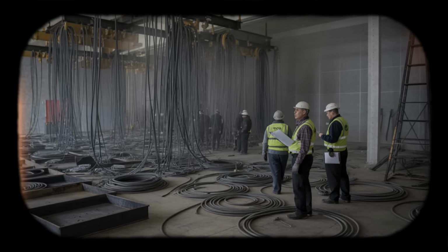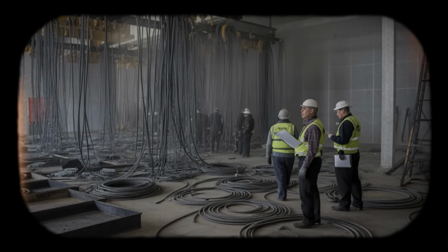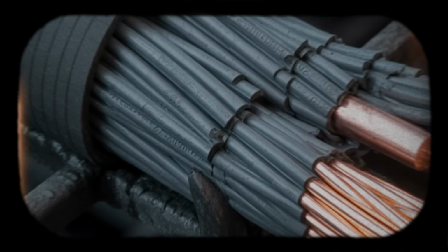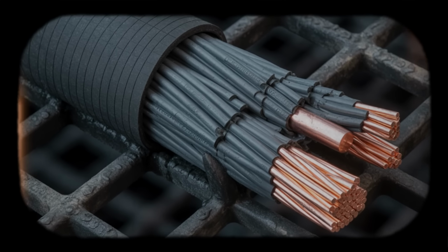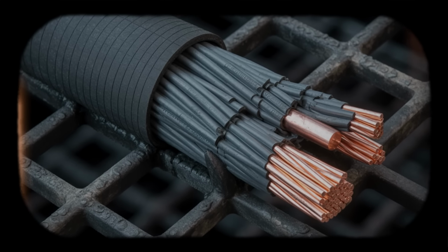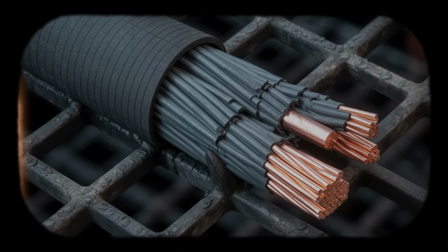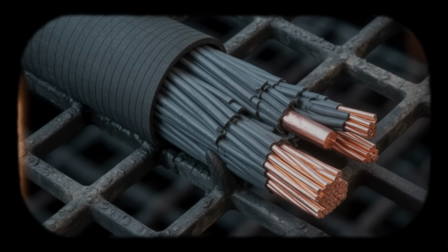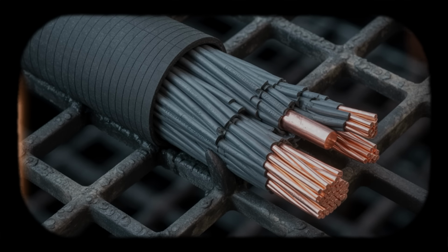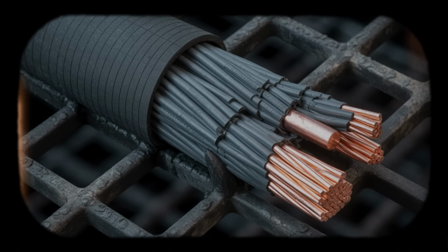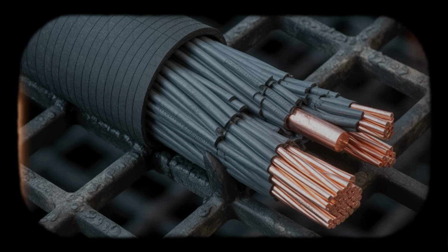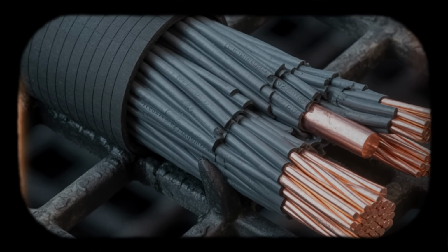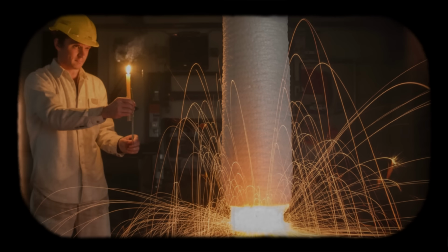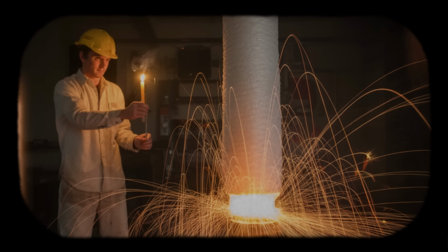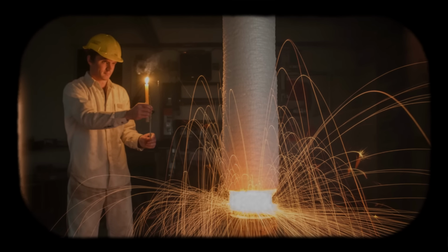but the design included one shared space, the cable spreading room beneath both control rooms. It was an efficiency measure during construction. Rather than building two completely separate cable routing facilities, engineers created one room that served both units. Cables from Unit 1 and cables from Unit 2 converged in the same trays, passed through adjacent penetrations, and shared common support structures. The fire ignited in a penetration that served primarily Unit 1 circuits, but as flames spread along cable trays, they encountered Unit 2 conductors in the same trays.